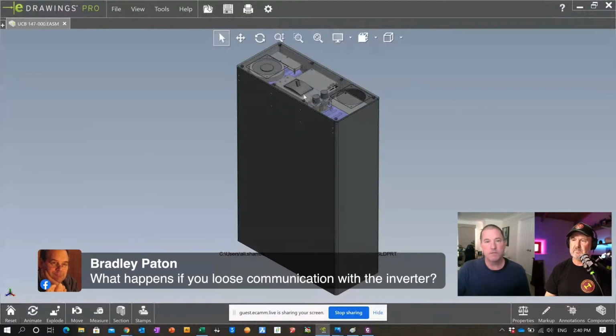There's a built-in shunt trip inside the MCCB, so we can fire the circuit breaker to turn off, and the boards inside work autonomously. Within our software there's a main processor, an Arduino processor, which monitors the battery. If it sees something's wrong, if any cell is outside the voltage window it wants to be in, or if there's too much power coming through, there's also a current sensor in here which I haven't shown you yet.